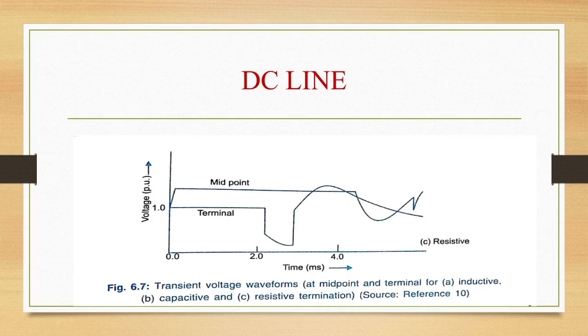Sixth, with capacitive termination, the lowest limit on the dV/dt setting of the line fault protection is determined by the maximum fault resistance above which the fault will not be detected. It is necessary to provide a time delay in the operation of the protection using dV/dt to prevent the tripping of the healthy pole. Typically, a time delay of about 3 milliseconds may be adequate.